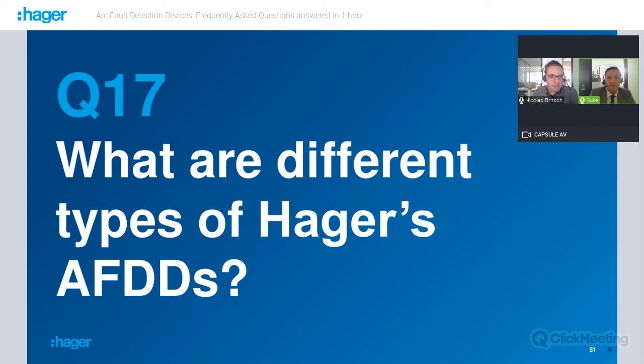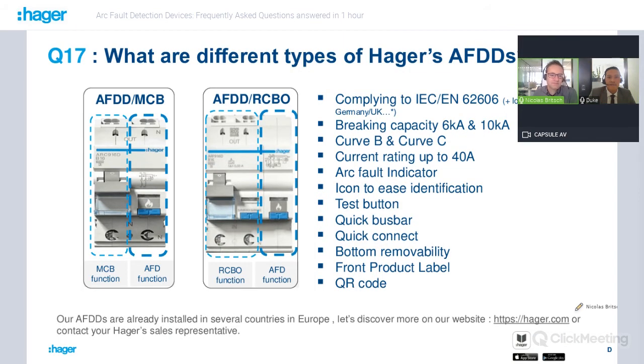Okay, now a question for you, Duke. What are the different types of Hager's AFDDs? Okay, at Hager we have a complete range portfolio of AFDD. We have two types, combined with MCB and combined with RCBO. So we can see here that our products have an icon for easy identification of an AFDD among the other modular devices such as RCDs or MCBs. We are of course compliant with IEC and EN standards, the AFDD standard, and local standards, with breaking capacity up to 10 kA, curves B and C, and current rating up to 40 amps.